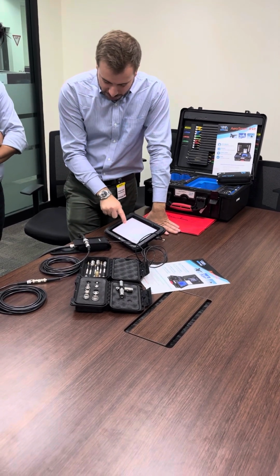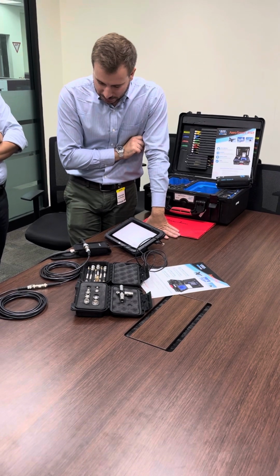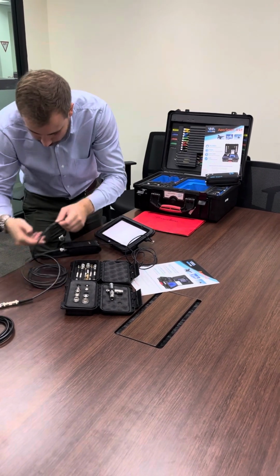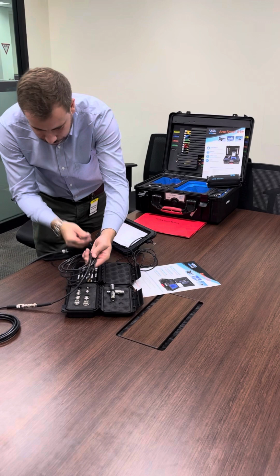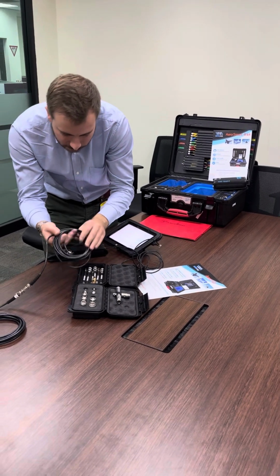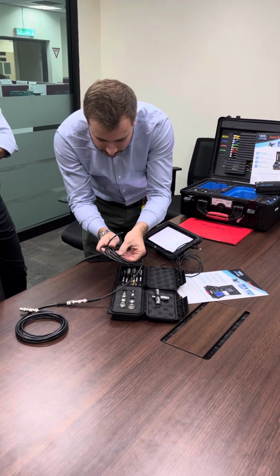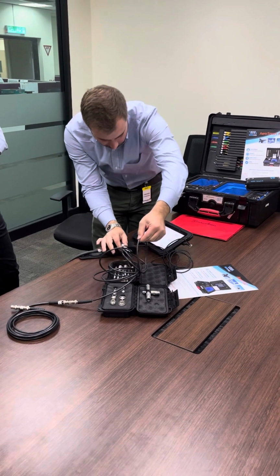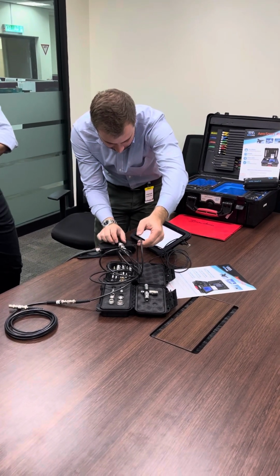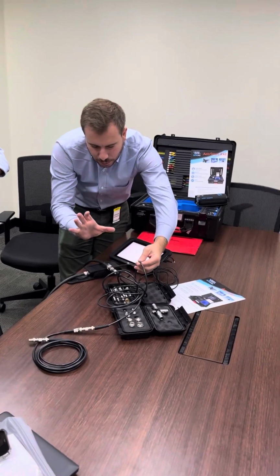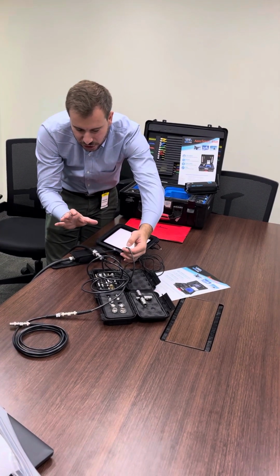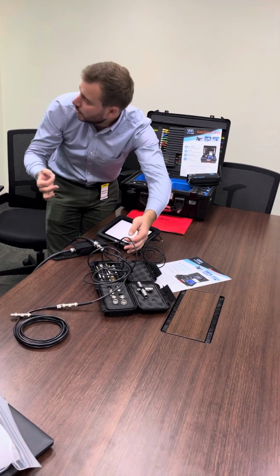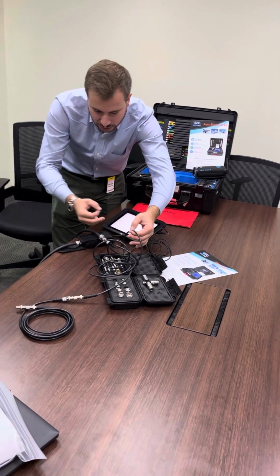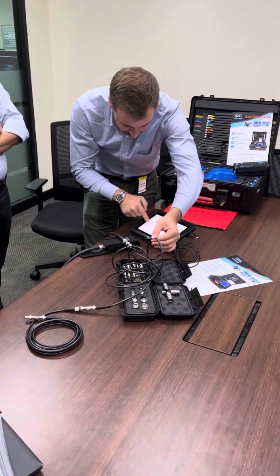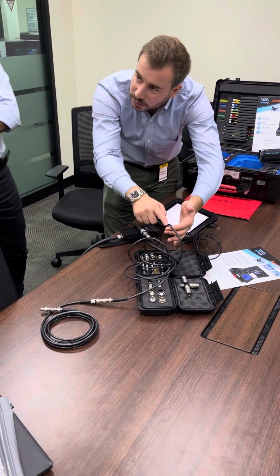At 1 meter we can see that we have a quite important peak. And 1 meter, if I deploy the thing here, this corresponds to this. If you see, if I touch with my finger, the peak is moving. Okay, so that's a pretty important fault. You see that the shield is damaged. The continuity is still good, but the shield is damaged. So at 1 meter, this is the fault which is here.